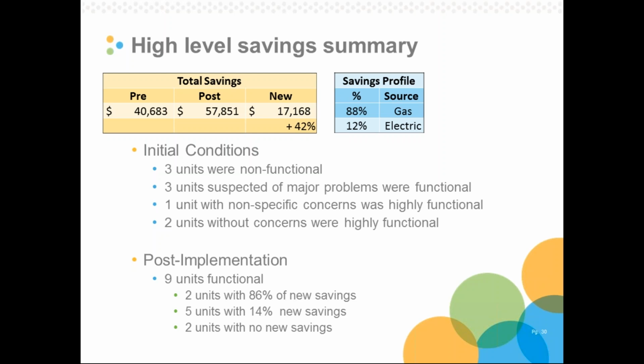If we look at the savings profile, the vast majority of these savings come from gas, almost 90%. We did find some electric savings, which is about 12%. I will say that this is with respect to essentially an EER 10 cooling system, so higher performance cooling systems will see less savings. So this is maybe a little bit optimistic, and still consistent with the idea that cooling savings are small and probably not the driving focus for implementing energy recovery in Minnesota.